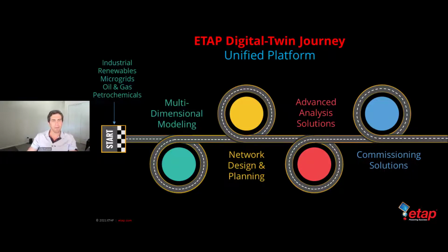Then we have network designing and planning. That would be the very common studies many people here are familiar with, including load flow, short circuit, arc flash, protection coordination. And we can move on to advanced analysis solutions, including transient stability, harmonics, motor starting—things that are a level or two above our run-of-the-mill standard applications.